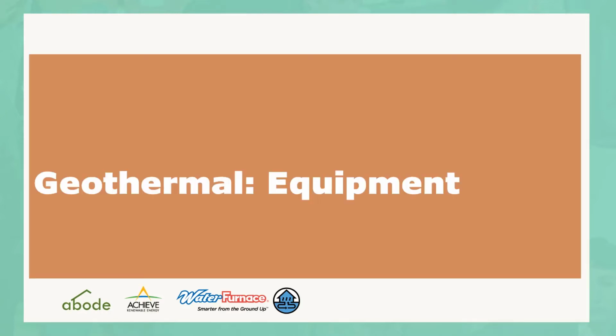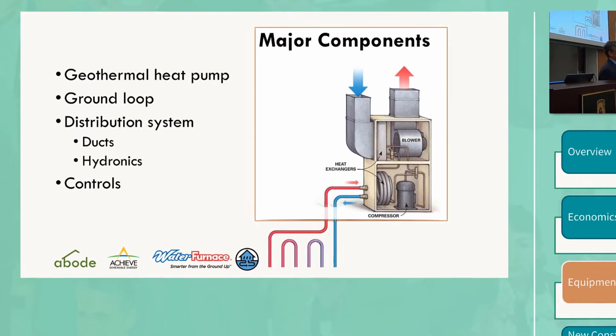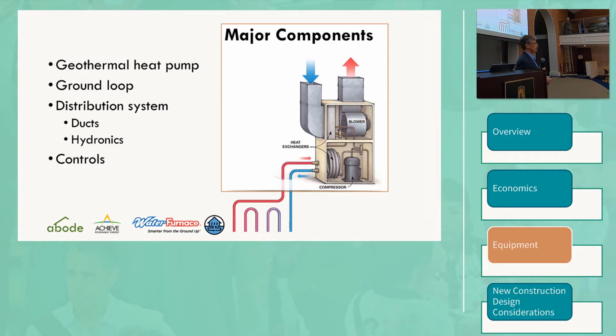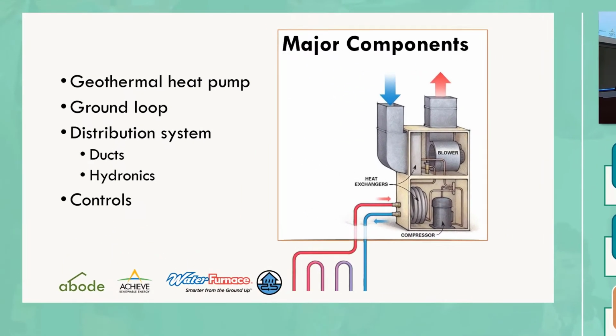All right, the geothermal equipment. Ground source heat pump systems are relatively simple on a conceptual level. You need the ground source heat pump itself, which is shown in this cartoon, has some heat exchangers and a refrigeration compressor and a blower in the case of a ducted system. You have the ground loop, or the ground heat exchanger, and a distribution system, which in this cartoon is a ducted system, but it could just as easily be hydronics. And then the controls are where things get fancy, where we can start doing zoning and internet connectivity and monitoring and all that stuff, and we'll talk about that in a little while.